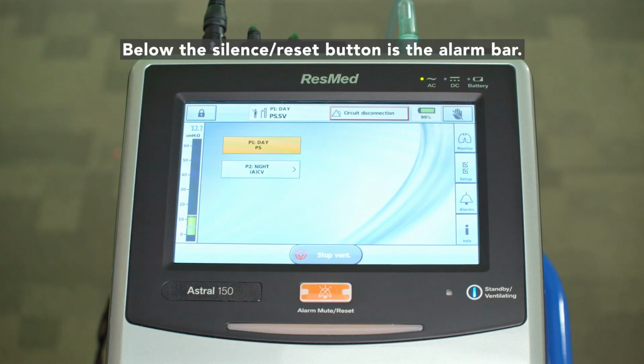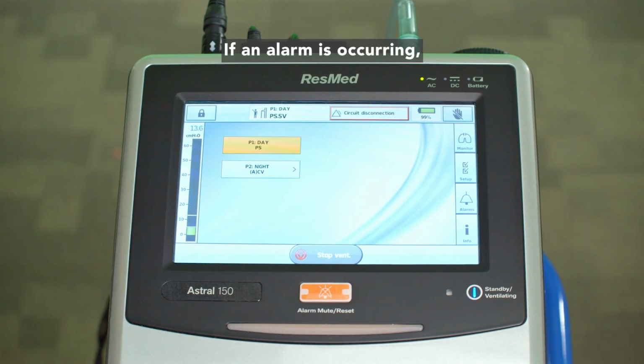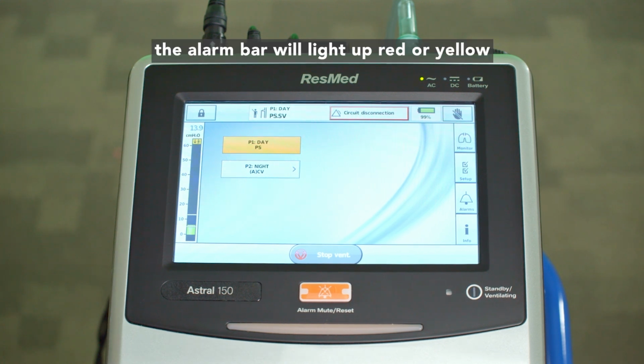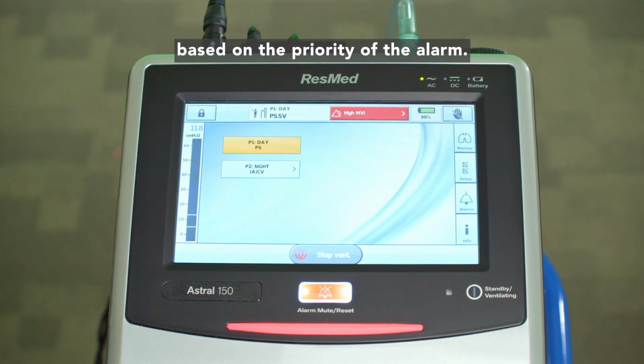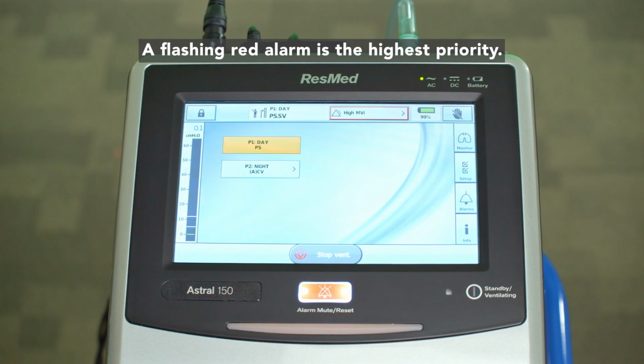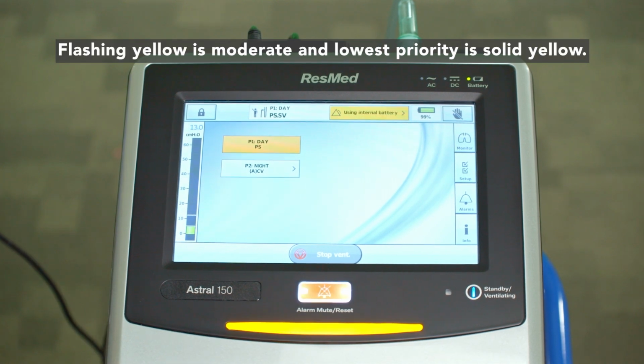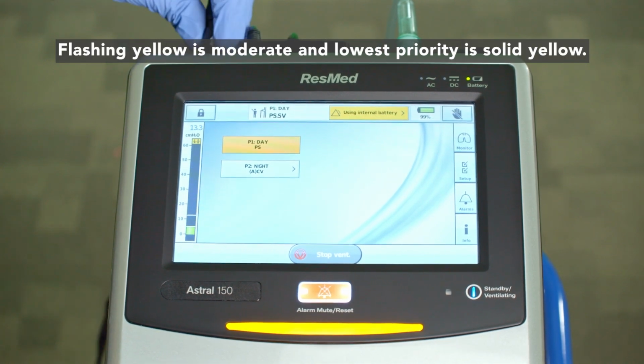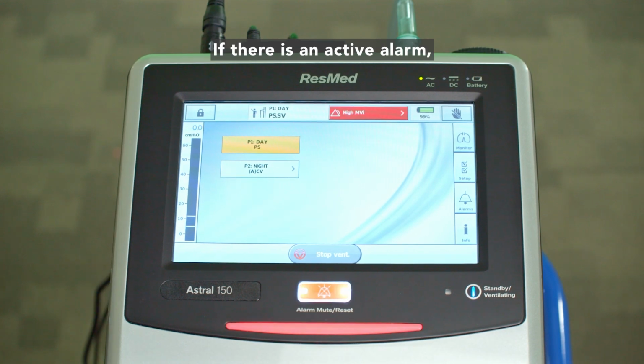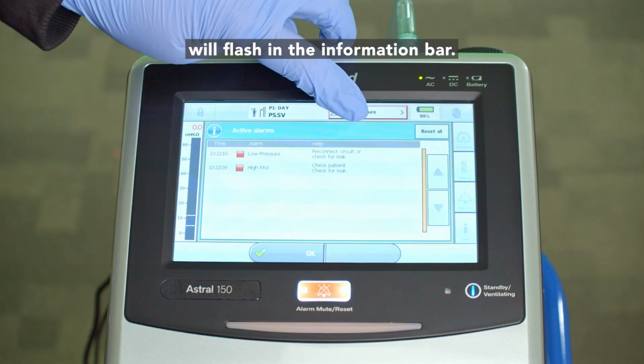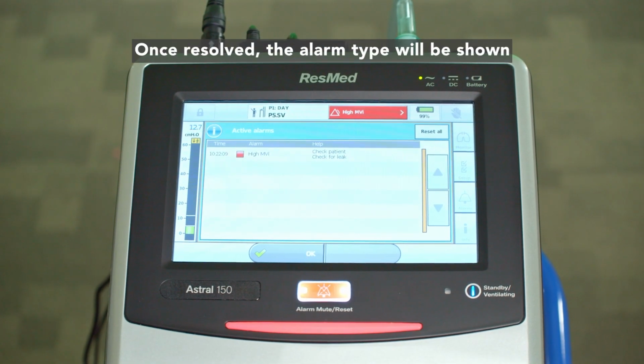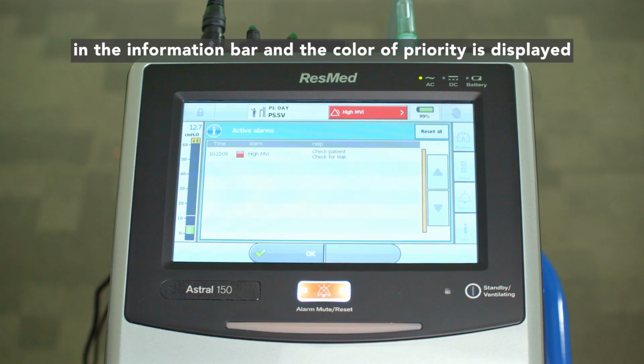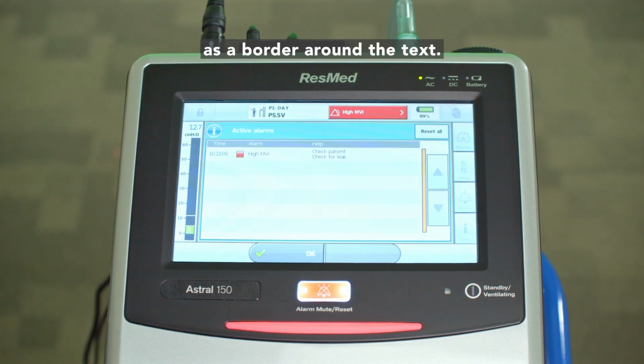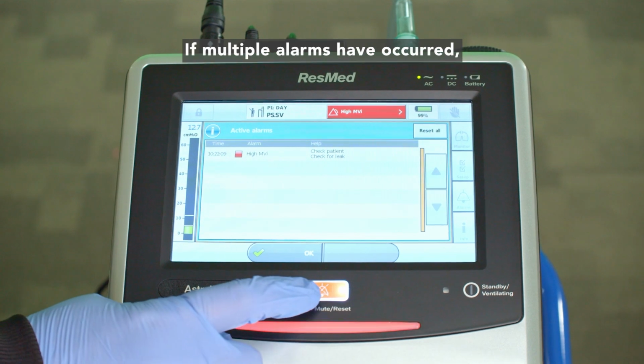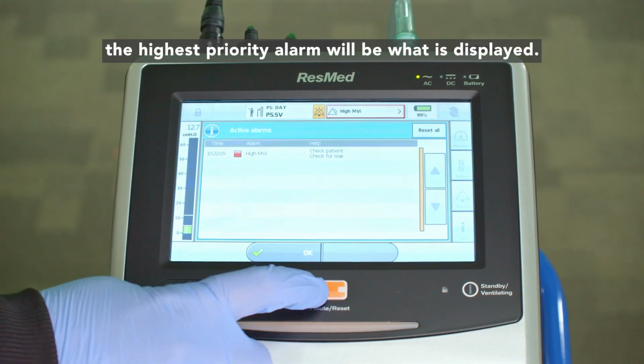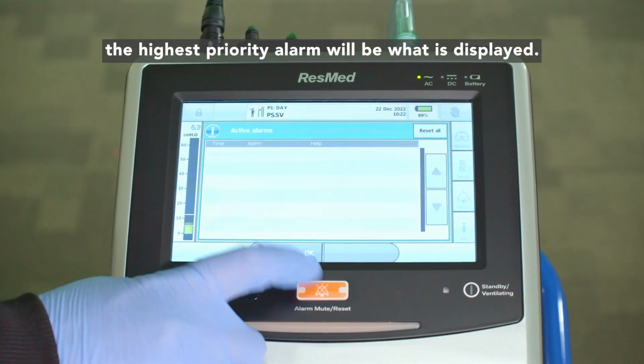Below the silence reset button is the alarm bar. If an alarm is occurring, the alarm bar will light up red or yellow based on the priority of the alarm. A flashing red alarm is the highest priority. Flashing yellow is moderate, and lowest priority is solid yellow. If there is an active alarm, the type of alarm and priority color will flash in the information bar. Once resolved, the alarm type will be shown in the information bar, and the color of priority is displayed as a border around the text. If multiple alarms have occurred, the highest priority alarm will be what is displayed.